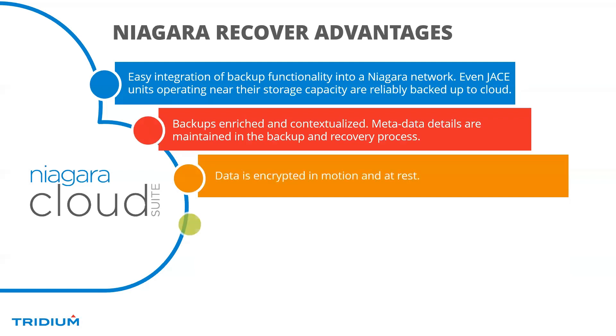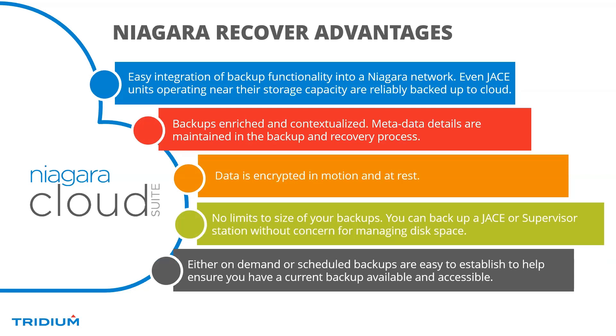The advantages include easy integration into your Niagara network, and even JACEs operating close to storage capacity can now reliably back up to the cloud. Backups are enriched and contextualized — all metadata details are maintained and you can add notes in the backup and recovery process. Data is encrypted both in motion and at rest. There are no limits to the size of backups, so you can back up a JACE or supervisor without worrying about disk space. Setup takes about 10 to 15 minutes and your backup is there whenever you need it.